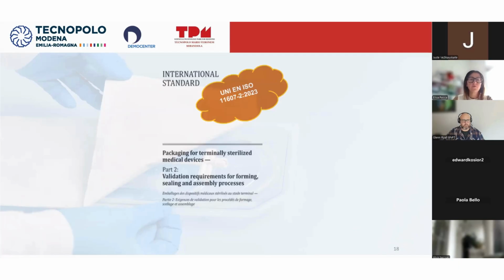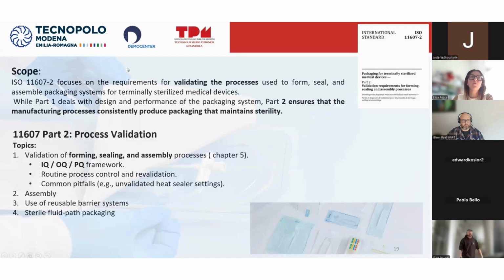So just a few points about the ISO Part 2. The scope of Part 2 is focused on the requirements for validating the process used to form, seal, and assemble packaging systems for terminally sterilized medical devices. While Part 1 deals with the design and performance of the packaging system, Part 2 ensures that the manufacturing process consistently produces packaging that maintains sterility. So the main topics of Part 2 are validation for forming, sealing, and assembly in Chapter 5, so the IQ, OQ, PQ framework, routine process control and revalidation, common pitfalls, assembly, reusable barrier systems, and sterile fluid packaging.